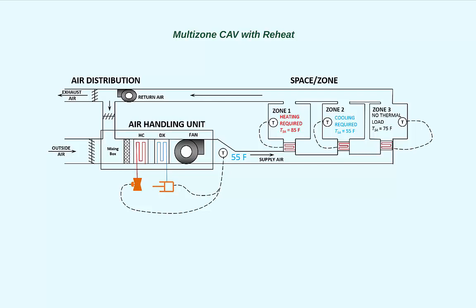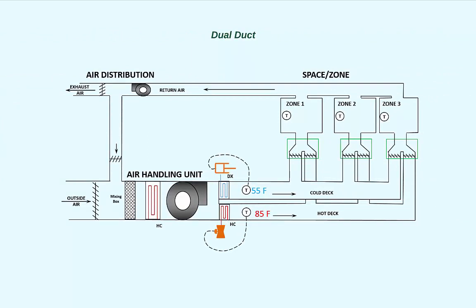This allows cooling to be delivered to zone 2, heating to be delivered to zone 1, and ventilation to be supplied to zone 3 without heating or cooling. If the mixed air temperature entering the air handling unit is less than 55, it would be increased by the heating coil. If you understand the control of these two designs, you understand how all DX systems are controlled. Either they are controlled based upon the zone temperature or the discharge air temperature. In a dual duct design, the refrigeration cycle is controlled based upon the discharge air temperature of the cold deck. Thermal comfort is achieved by mixing the two air streams at the zone.